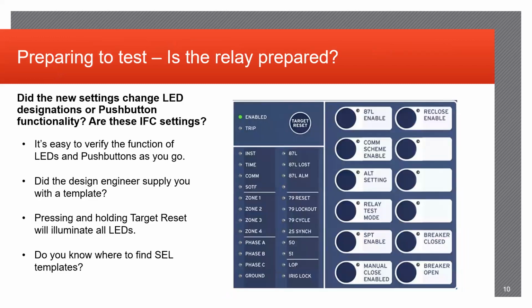So is the relay prepared? Did the new settings change any LED designations, push button functionality, stuff like that? So if you are testing a previously in service relay and you get a new form of issued settings, they may not line up directly with the push button and LEDs from the previous settings. So you must identify, are there any changes? Are the LED and push button labels the same? Does stuff change? And if stuff did change, do you need to get a new template for the labels? In which case, do you know where the labels are?